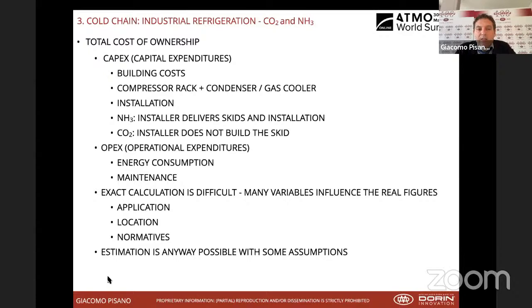However, with the latest development in terms of CO2 cycles, I'm referring to parallel compression, ejector, adiabatic coolers, and the like, CO2 can pretty much be aligned to ammonia also in terms of energy efficiency. Clearly, maintenance costs are totally different also in terms of compressors. Normally, compressors are designed in a way that they can run till their end of life without preventive maintenance. So they can run for 50, 60,000 hours without being inspected, and then they can be simply replaced.